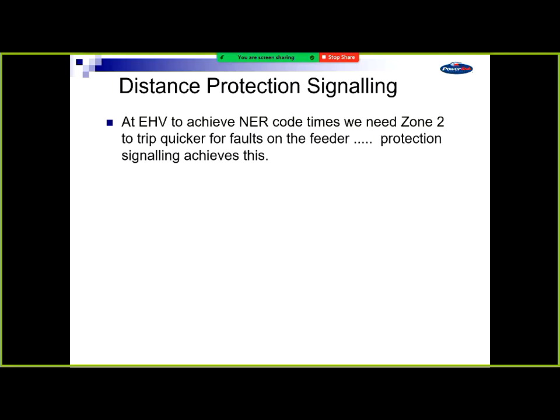And to me, it's also looking at the consequences. So when I set a short feeder, I'm happy to set the zone 2 time delay a bit quicker so the remote zone 2s don't go before or at the same time as I do. And it was those remote zone 2s that cleared the fault on the generator transformer. The problem with that, all the feeders into that substation tripped, which was good because nothing else saw the fault and cleared it, so we did clear it. But if you had a distance relay on that feeder and the zone 2 set to 100, 200 milliseconds, we would have cleared just that feeder a little bit quicker and less impact on the network. That's the consideration when you're doing these settings. You just need to think.